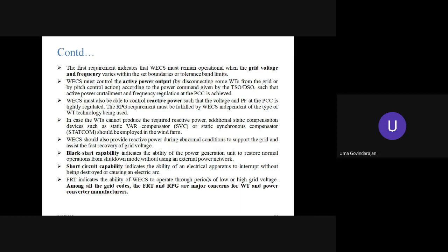The first requirement indicates that the wind energy conversion systems must remain operational. Very important, they must remain operational when the grid voltage and frequency vary within the set boundaries or tolerance band limits. So when the wind generator is connected to the grid, even if there are variations in the grid voltage and frequency, the wind generators should not come out of synchronism or pull out from the grid. It should stay connected with the grid. That is the first requirement.